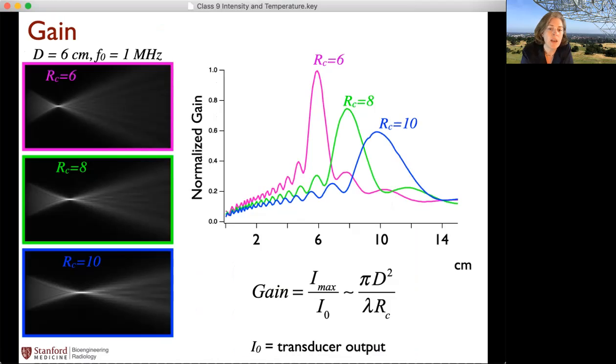So one of the beam characteristics that we haven't talked about so far was the gain. If we define the gain as the intensity at the focus divided by the intensity right at the surface of the transducer, then what we see is it's related in this way. The larger the transducer, the more the gain. The smaller the radius of curvature, the more the gain. So in this situation, where we had the same diameter on the transducer for these 3 different simulations, but all we did was change the radius of curvature, we see that there was more gain on the one with the smaller F number, the smaller radius of curvature. So that's one point to notice.